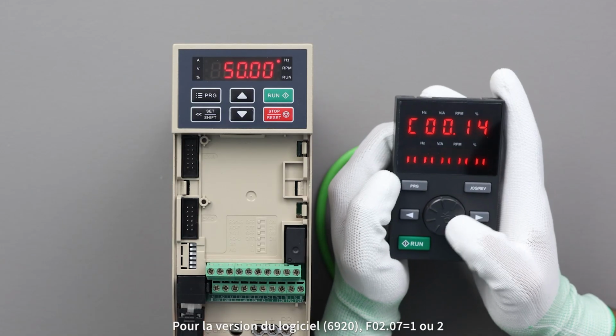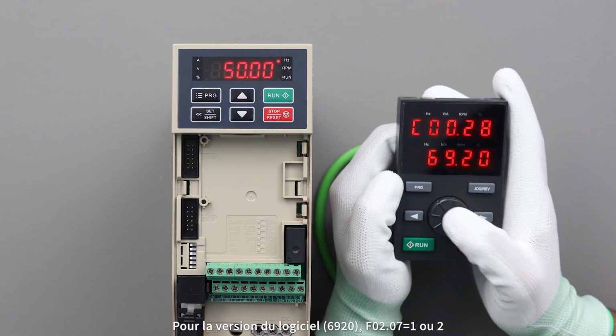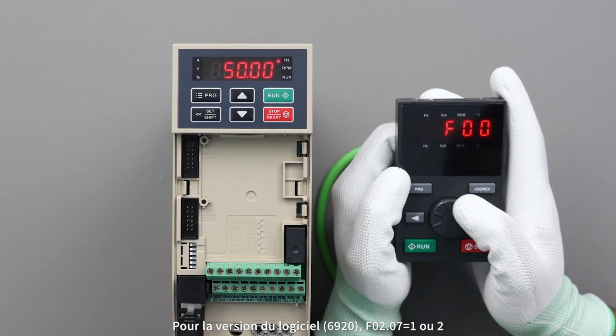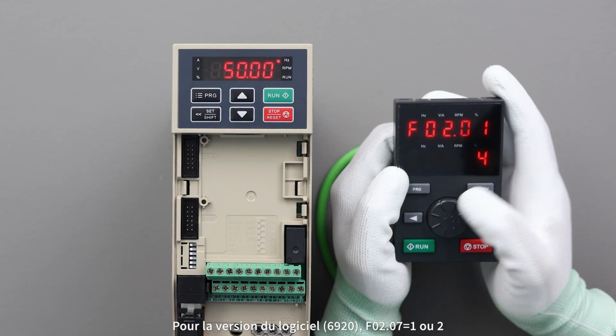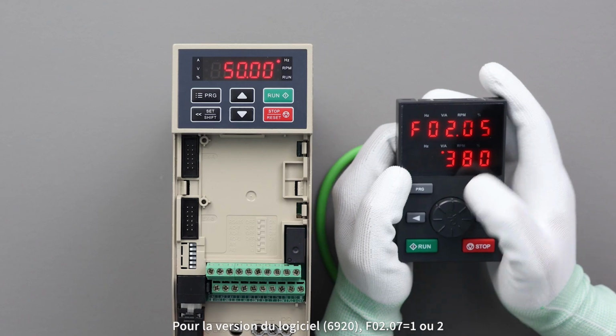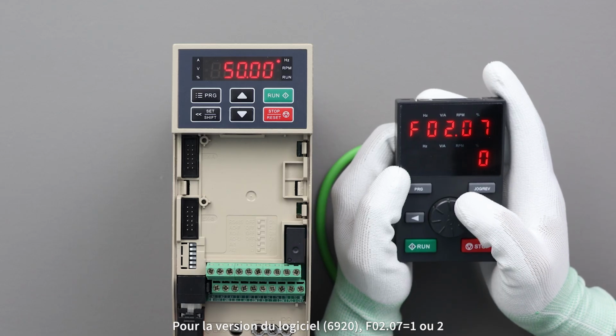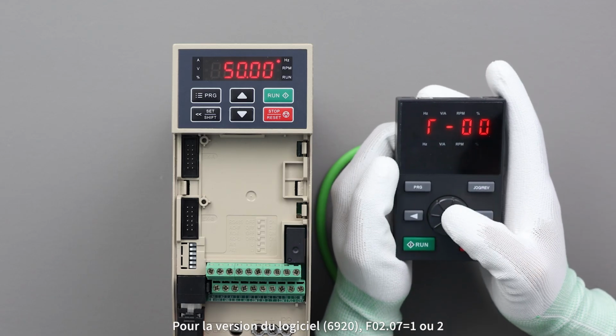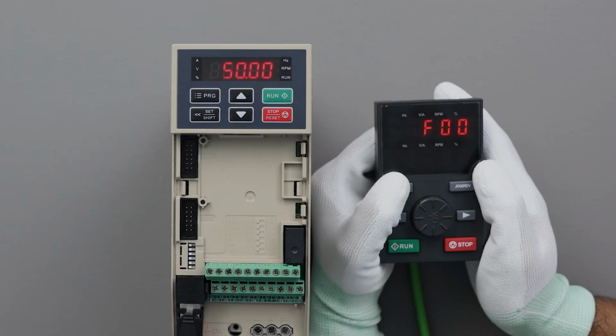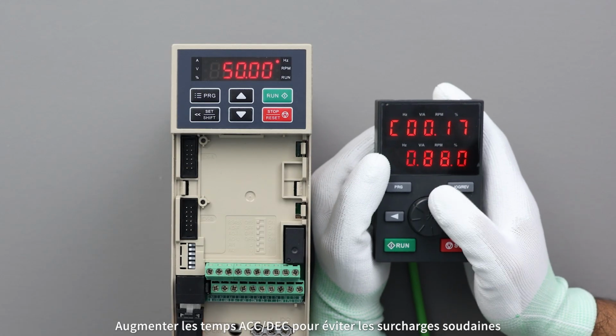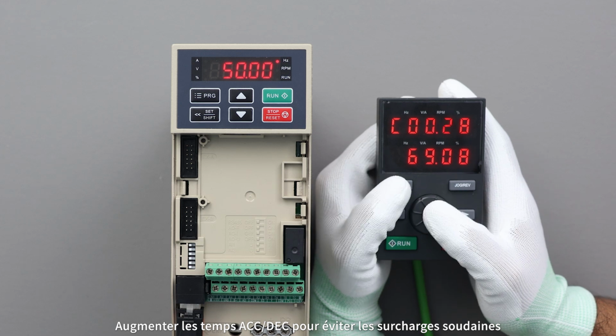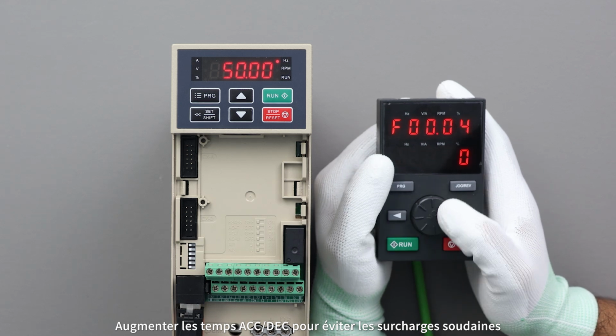For software version 6920, set F02.07 to 1 or 2. Increase acceleration and deceleration time to prevent sudden overloads.